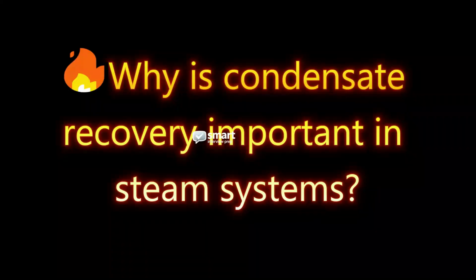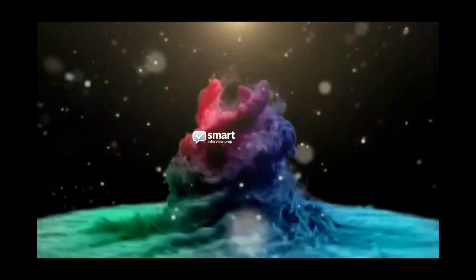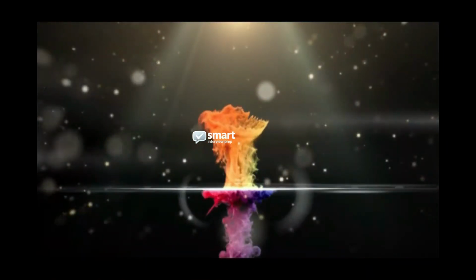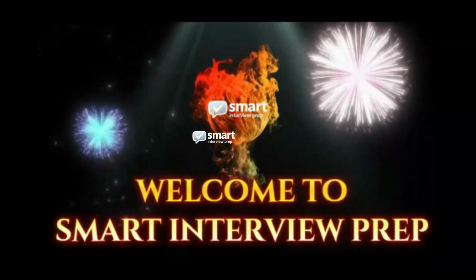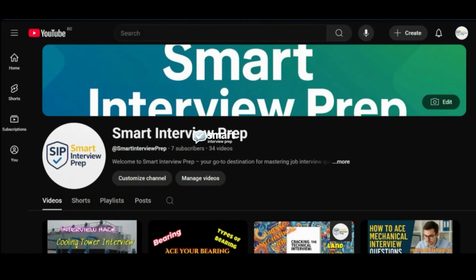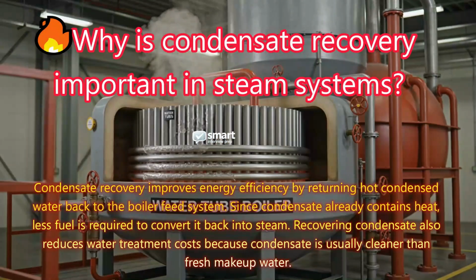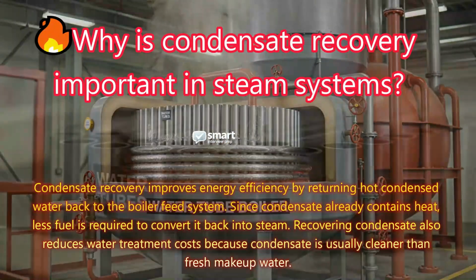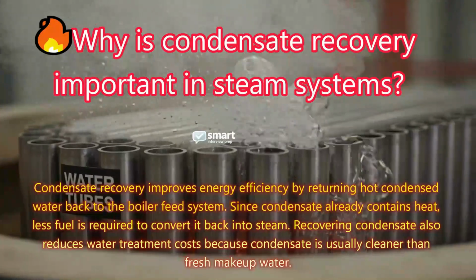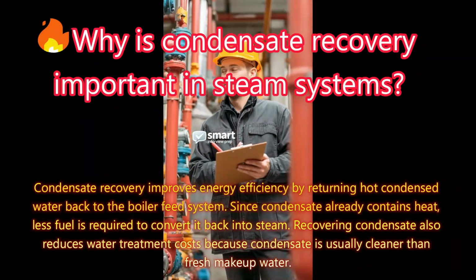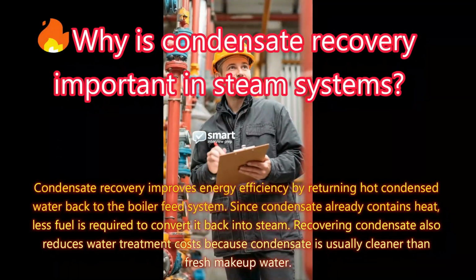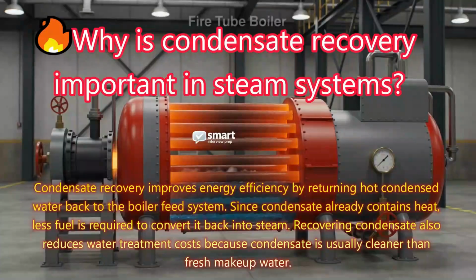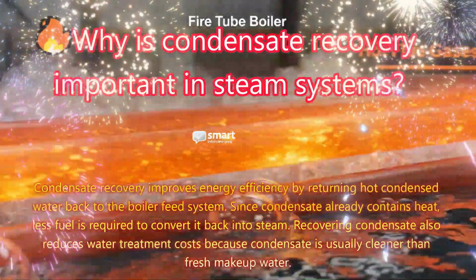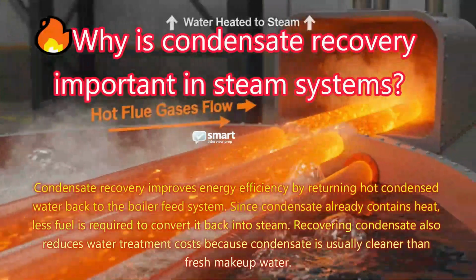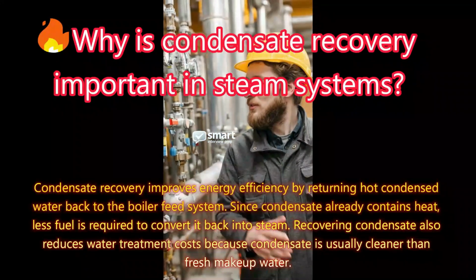Why is condensate recovery important in steam systems? Answer: condensate recovery improves energy efficiency by returning hot condensed water back to the boiler feed system. Since condensate already contains heat, less fuel is required to convert it back into steam. Recovering condensate also reduces water treatment costs because condensate is usually cleaner than fresh makeup water.